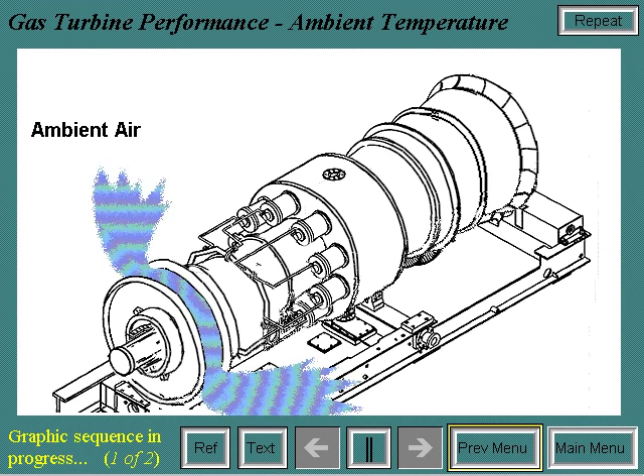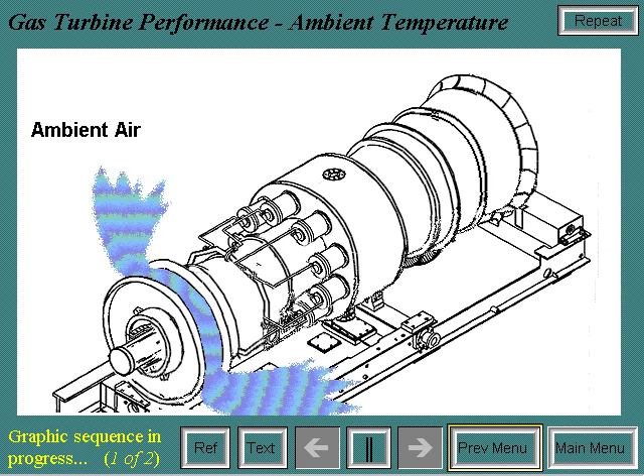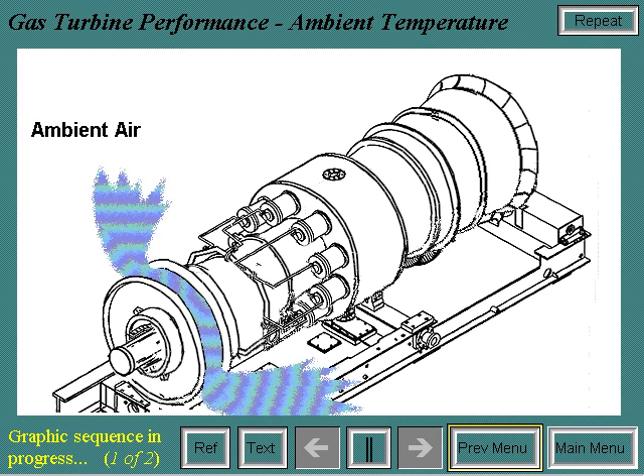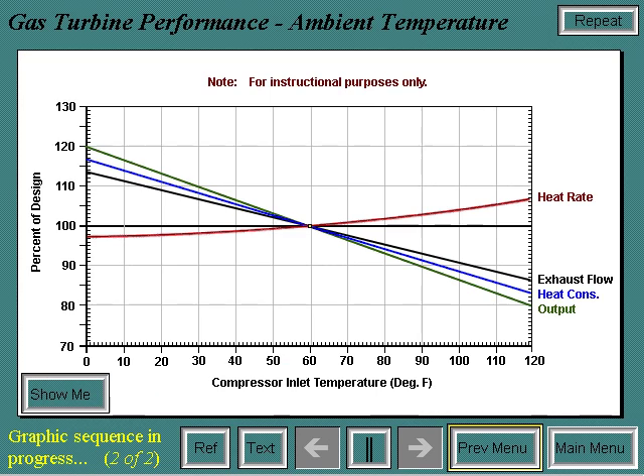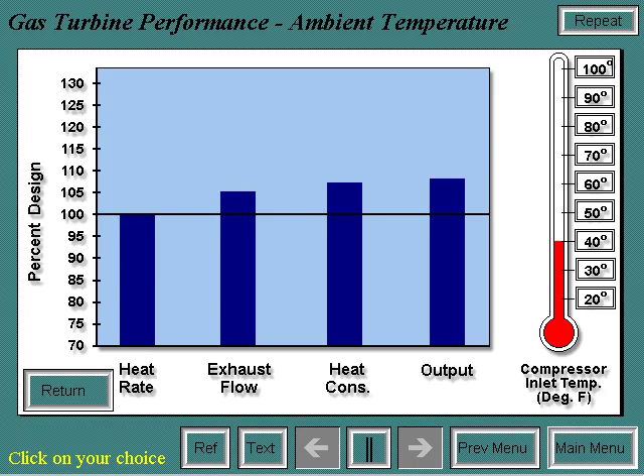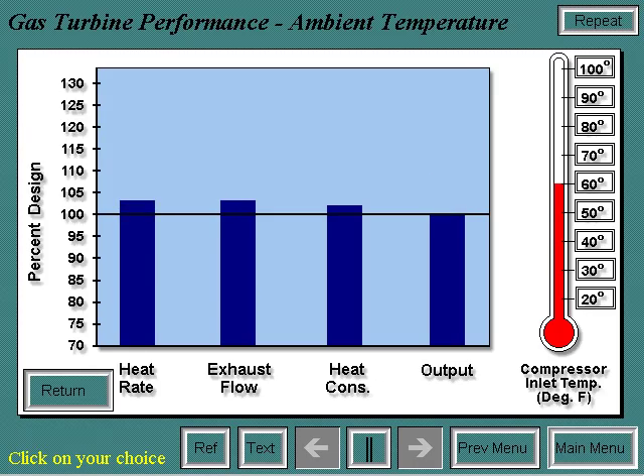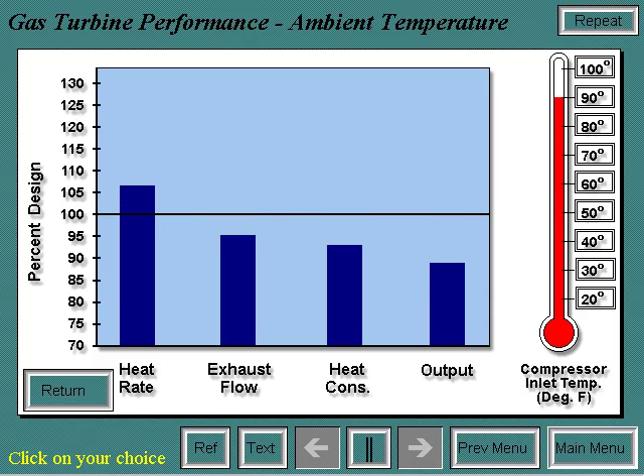Since the gas turbine is an ambient air-breathing machine, its performance will be changed by anything affecting the mass flow of the air intake to the compressor. The most obvious are changes in the reference conditions of 59 degrees Fahrenheit and 14.7 PSIA. Depending on the unit's cycle parameters and component efficiencies, ambient temperature will affect the air mass flow, which in turn will change output, heat consumption, heat rate, and exhaust flow.